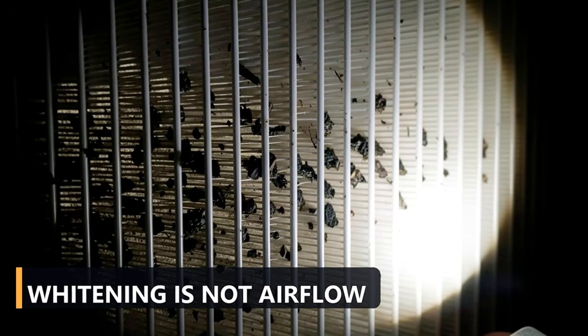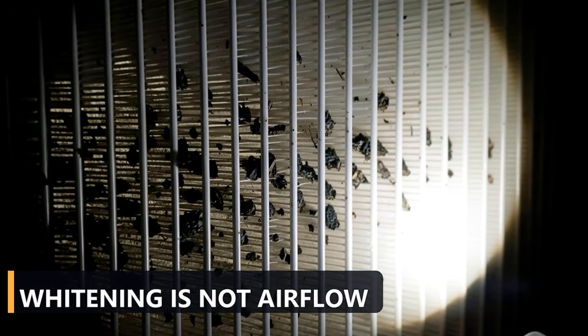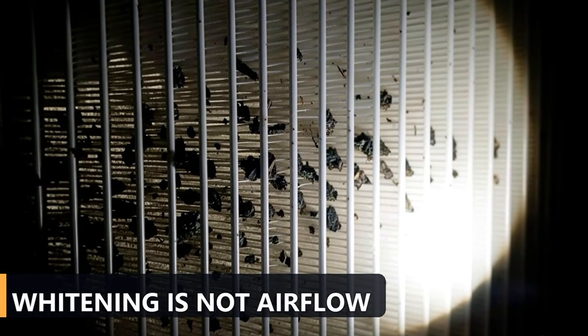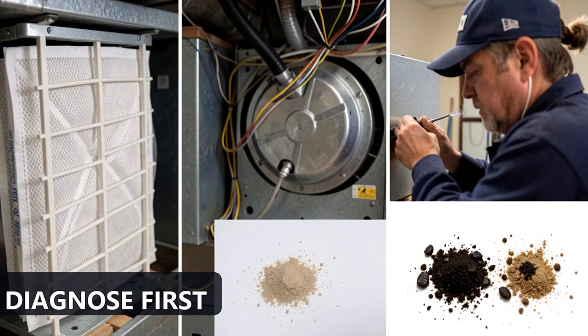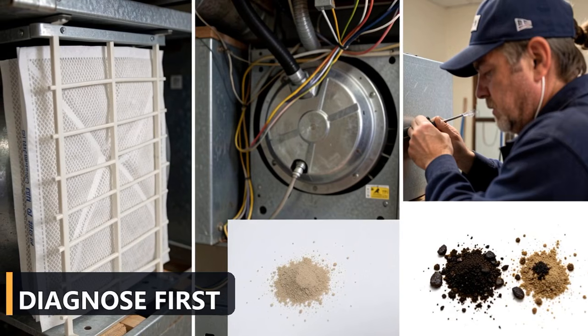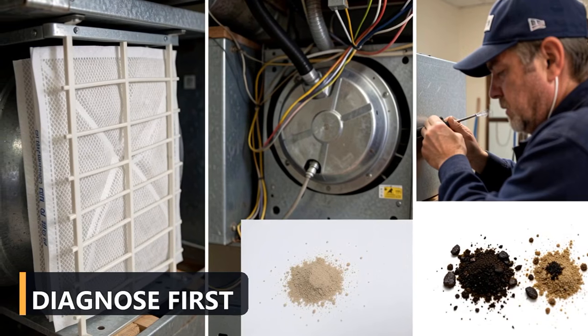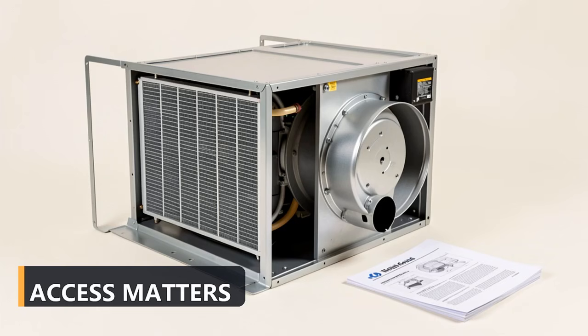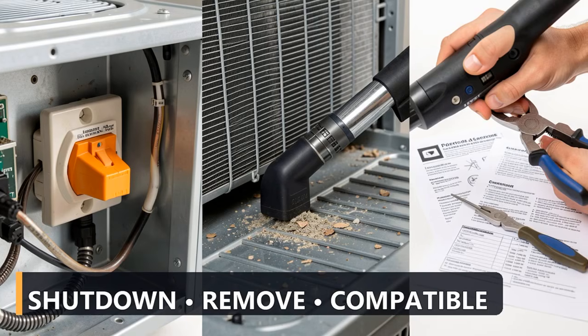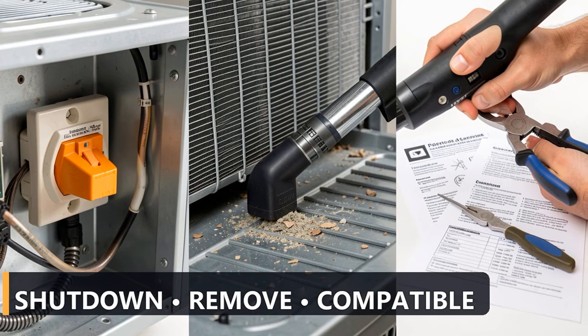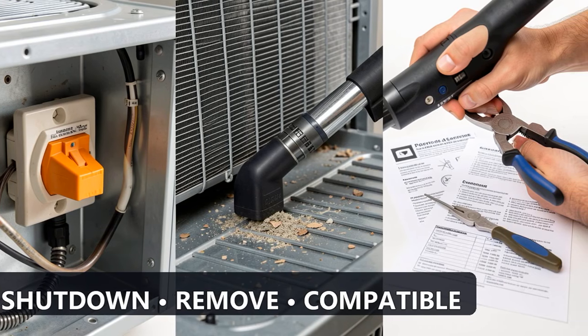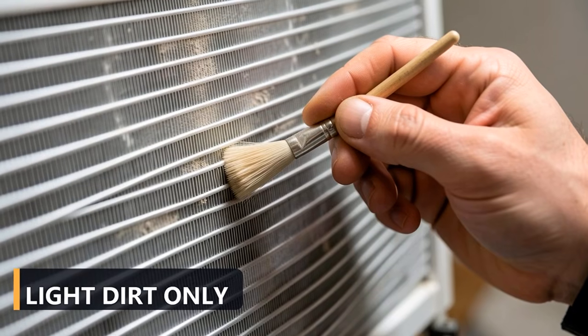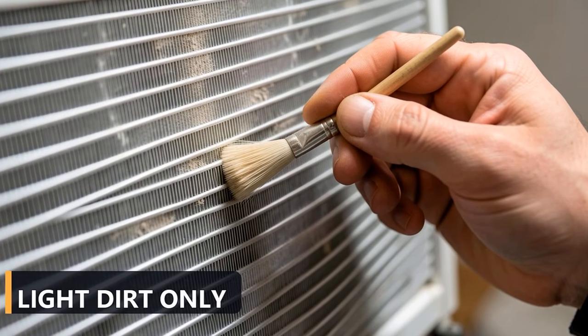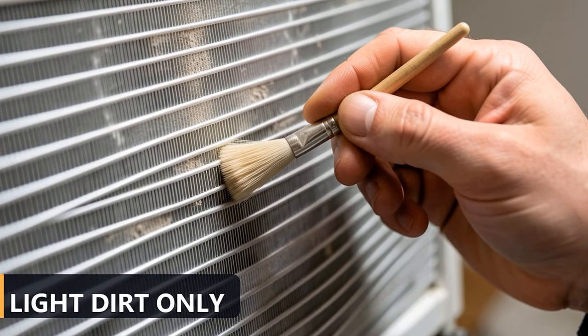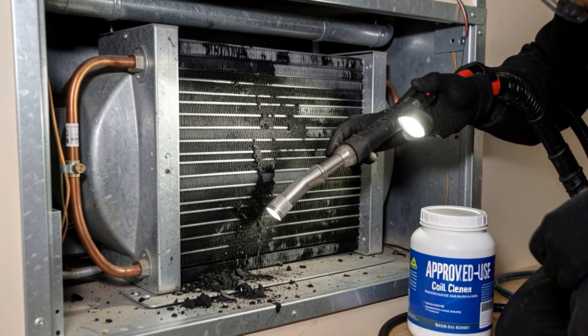Professional coil cleaning begins with diagnosis. Is the filter missing or overloaded? Is the blower moving enough air? Is the dirt dry and loose, or is it bonded with oil? Is the coil accessible from both sides? Manufacturer guidance commonly calls for shutting down the system, removing loose debris carefully, and using a compatible coil cleaning method. Some light dirt may be removed with a soft brush or vacuum. Greasy material may require a mild detergent or a purpose-made coil product. The exact method depends on the equipment.